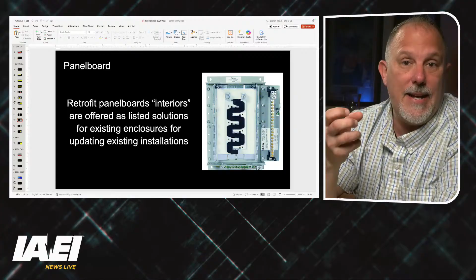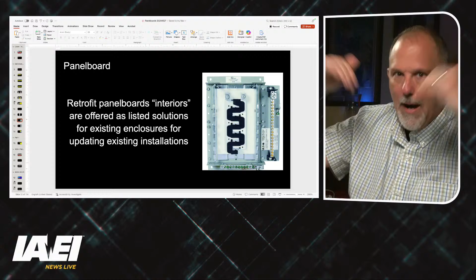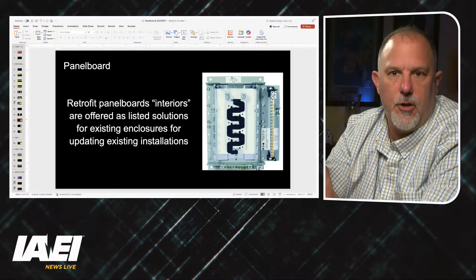So manufacturers came out with this solution of having an interior such that you take the contents of the existing interior out. You disconnect all the wires and take basically the panelboard out of the enclosure. Now you have a box with wires coming down into that box. Manufacturers came up with this concept of taking a panelboard and putting it in that same enclosure, because think about it, if the enclosure is in good shape, why take the enclosure out? The panelboard is going to be connected to the enclosure.